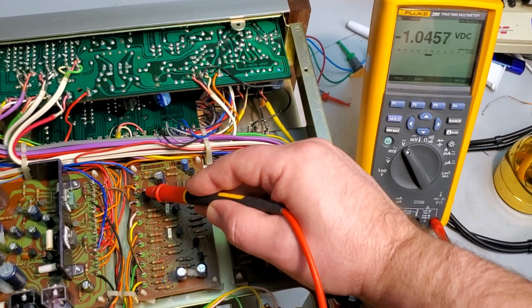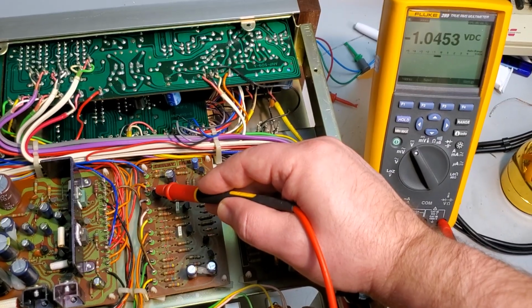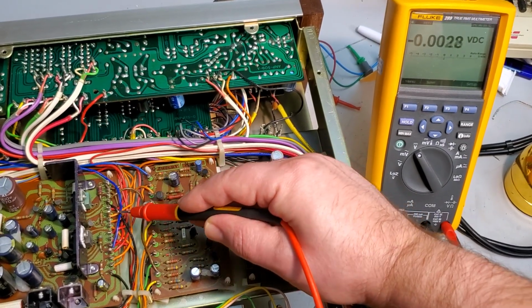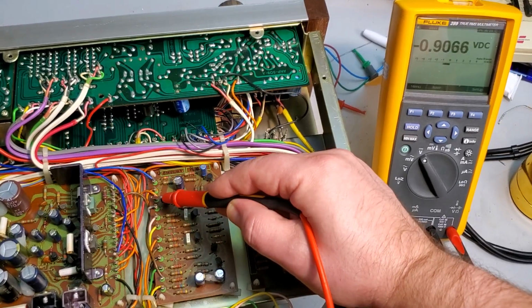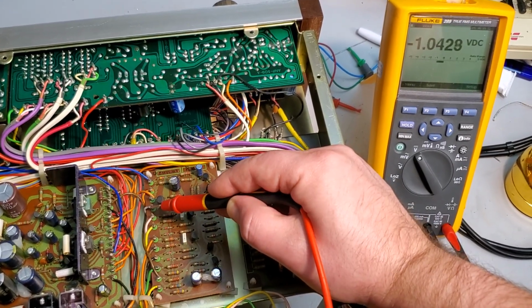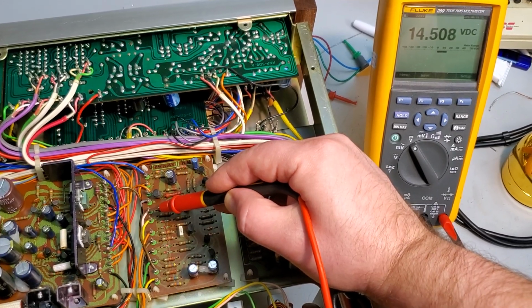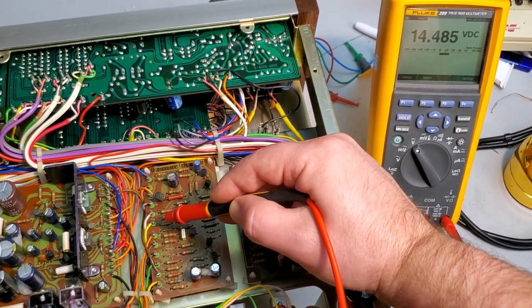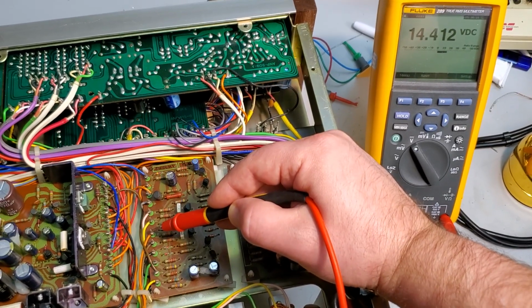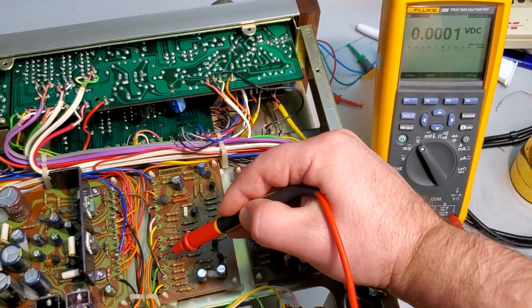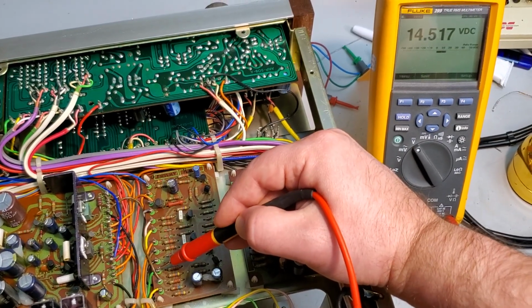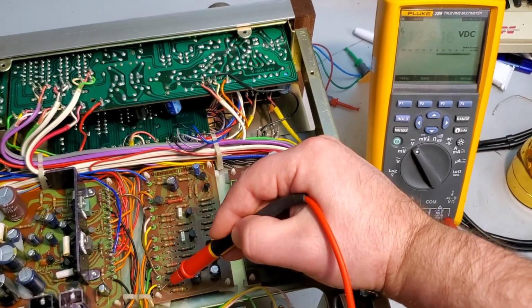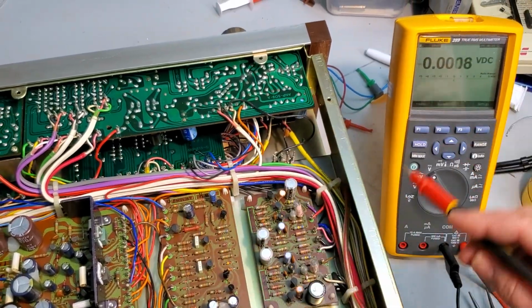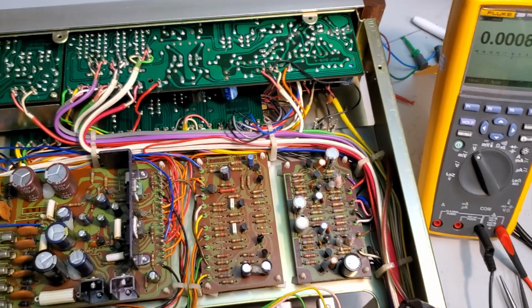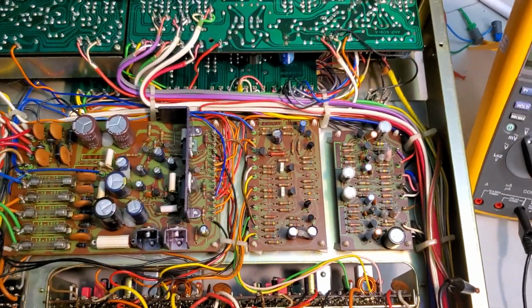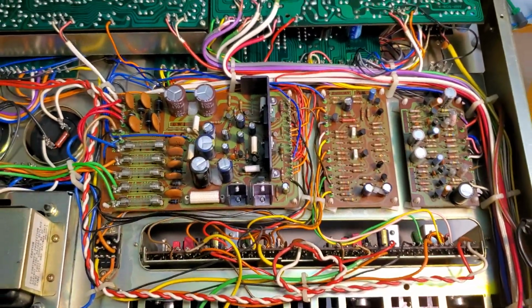I'm doing this because I note that on one of those orange terminals, it goes directly from the power supply to the protection circuit. That's probably our high output offsets right there. But again, no 24 or more volts to run that protection relay. This is the circuit that determines whether that relay is going to be powered up or not, so naturally it's switching that power, meaning it has to have 24 volt power somewhere, and it doesn't.